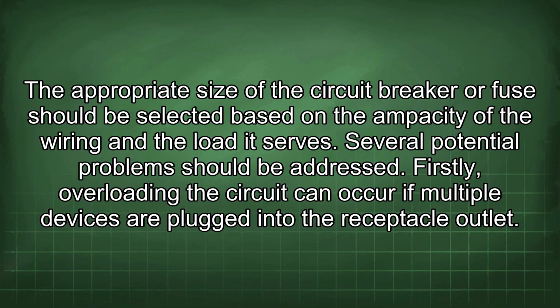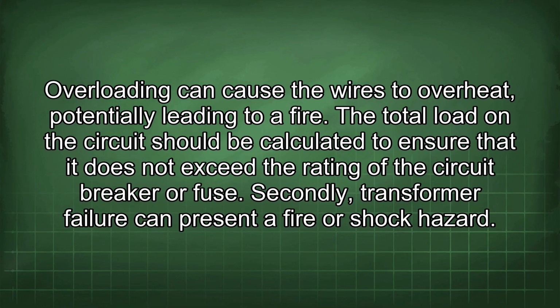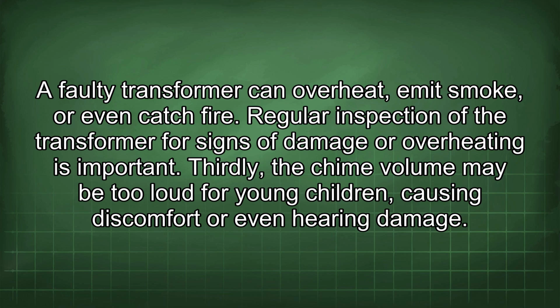Firstly, overloading the circuit can occur if multiple devices are plugged into the receptacle outlet. Overloading can cause the wires to overheat, potentially leading to a fire. The total load on the circuit should be calculated to ensure that it does not exceed the rating of the circuit breaker or fuse. Secondly, transformer failure can present a fire or shock hazard. A faulty transformer can overheat, emit smoke, or even catch fire. Regular inspection of the transformer for signs of damage or overheating is important.